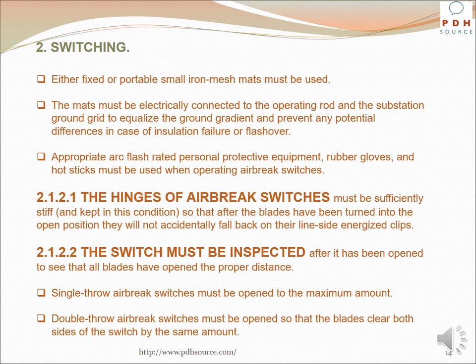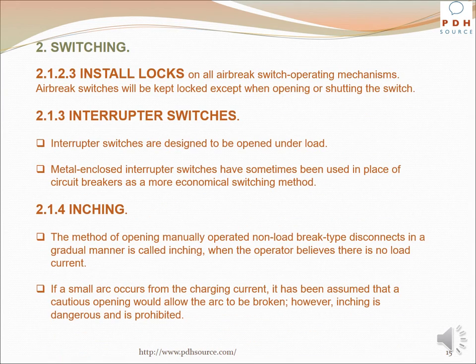Appropriate arc flash-rated personal protective equipment, rubber gloves, and hot sticks must be used when operating airbreak switches. The hinges of airbreak switches must be sufficiently stiff so that after the blades have been turned to the open position they will not accidentally fall back on their line-side energized clips. The switch must be inspected after opening to verify that all blades have opened the proper distance. Single throw switches must be opened to the maximum amount; double throw switches must be opened so that the blades clear both sides by the same amount. Install locks on all air brake switch operating mechanisms; they will be kept locked except when opening or shutting the switch.